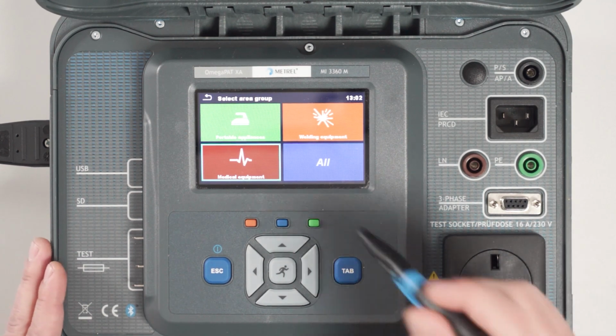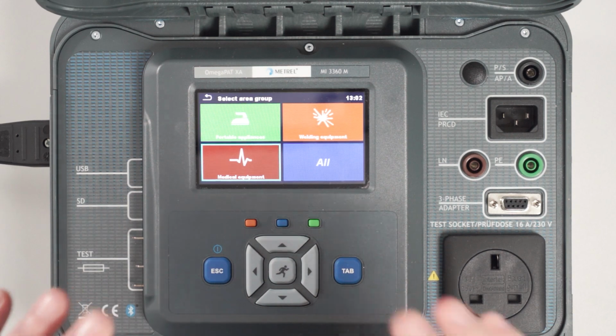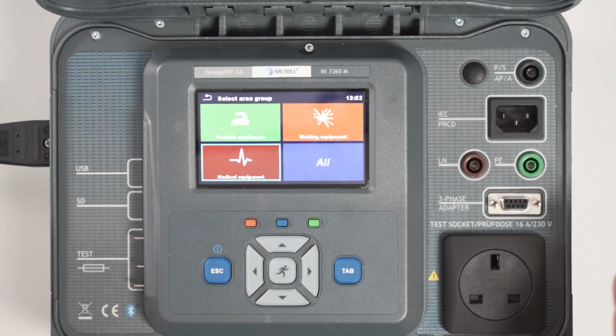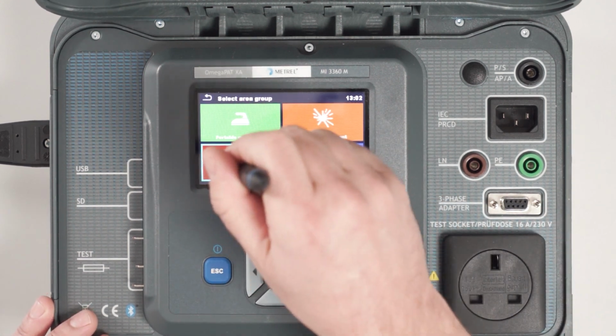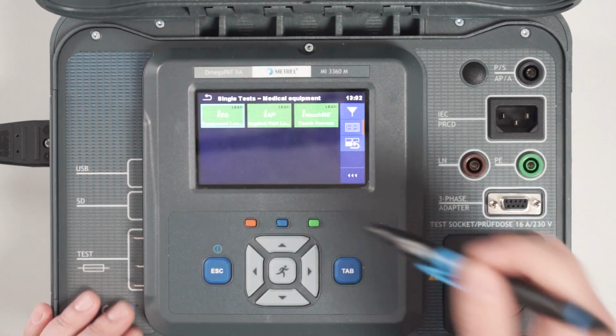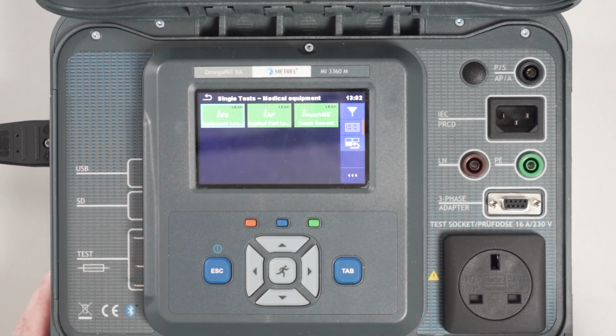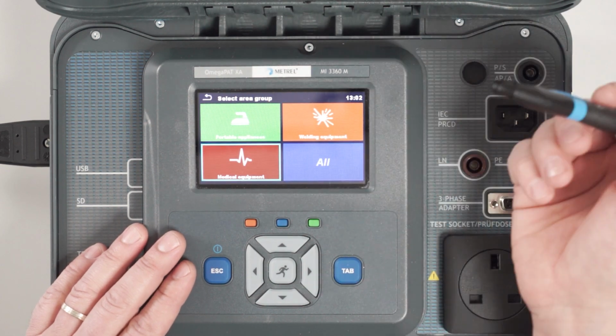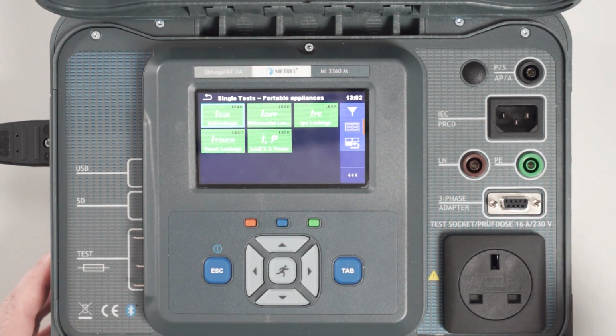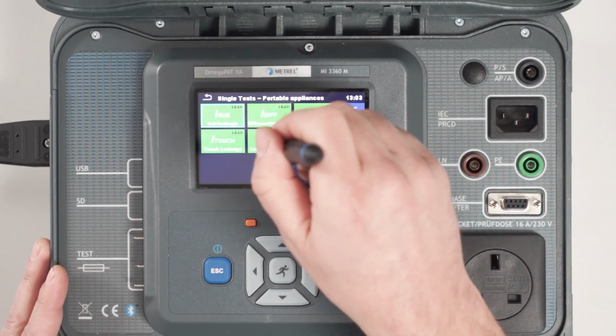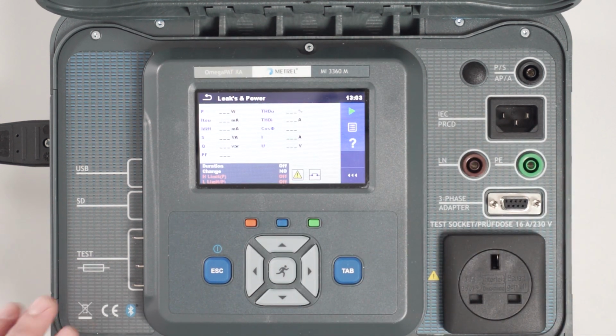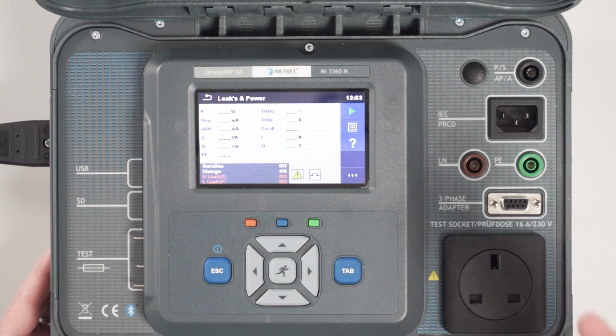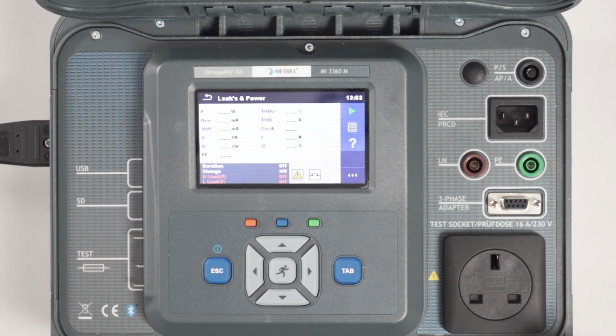The difference between different area groups is in whether we select just portable appliances. The selection of the measurements will shrink to just those that are applicable for testing of portable appliances. If I select medical equipment area group, then inside the leakages, for example, I will see the leakages which are applicable for medical appliances. So I see now equipment leakage and applied part leakage and touch leakage for medical devices. If I switch this area group filter to portable appliances, the leakages are now completely different. So we see substitute leakage, differential leakage, P leakage, which is a direct leakage method, touch leakage, and one very good feature or measuring function which is called leaks and power, which enables us to measure power of the device under test and also touch leakage and differential leakage at the same time.